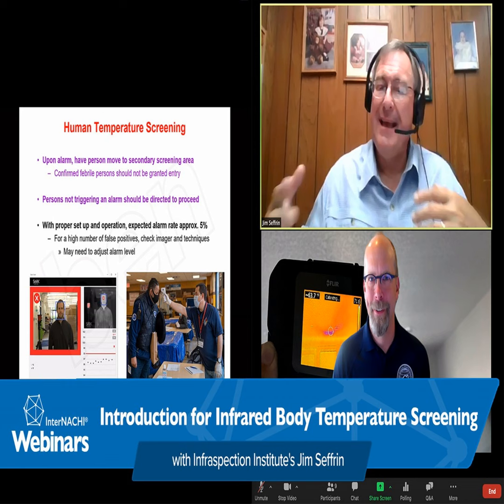Now, the FDA can return to stricter rules at any time. They could wait until the end of this pandemic when it's over, or they could change their minds tomorrow. We don't know. If they do that, it could preclude non-510K cleared imagers from being used in this application in the future. For countries following ISO 13154, there are no waivers or exemptions. Thermal imaging equipment must comply with the requirements laid out in ISO 13154 and the document that it incorporates by reference, the International Electrotechnical Commission 80601. Prior to purchasing an imager, make sure you check with appropriate authorities if this is an application that you want to become involved with for the instrument's compliance with regulations.